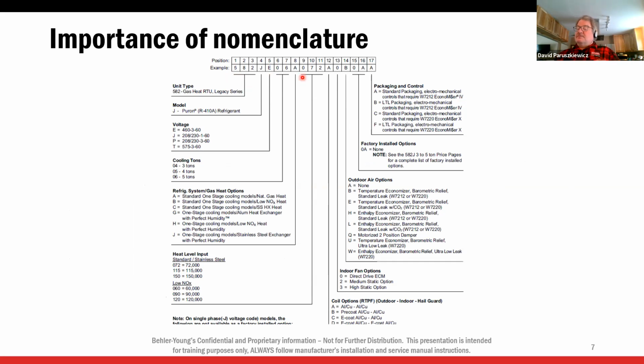All right, the model number. There are so many options on rooftop units and so many things change that all of that is buried in this model number sometimes. So you call a branch and say, hey, I have a 582JE and I need a blower motor for it. Well, that's not enough number. And I know it stinks every time the branch wants to say, hey, I need the whole product number. But we could guess wrong. So you need to get this entire 17-digit product number. And just some of the things, for instance, this 13th position here, that is the blower.